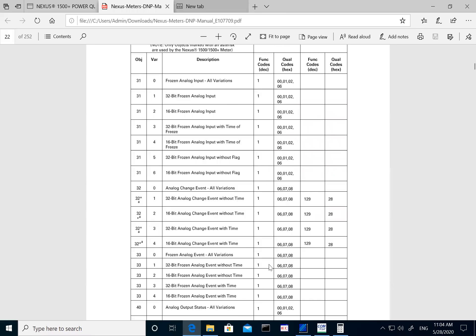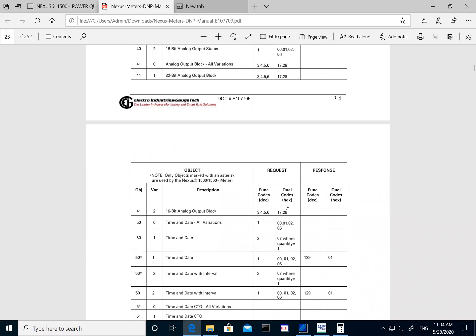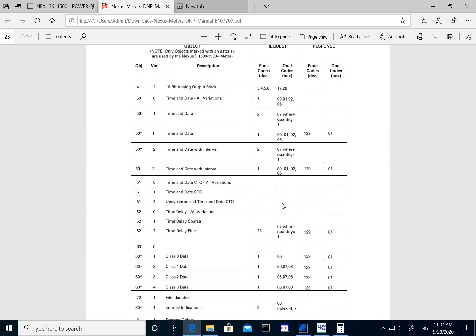The manual lists what function codes can be used to pull those objects, and what variations we support. In DNP, a 'variation' is basically a data type — so like integer, 16-bit, 32-bit, and so on. That is how DNP defines it using different variations. Once I go into the profile meter setup, I'll go into much more detail.